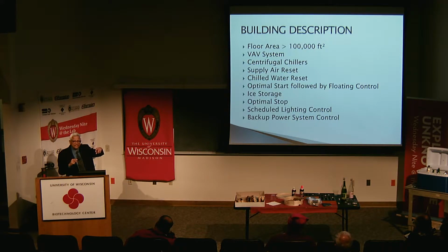Of course, it results in a little bit of extra chiller load, because now instead of keeping it at 78, you are using the optimal start to keep it at 73. But remember, this energy occurs during the off-peak period. So you are paying a lower cost in terms of the chiller energy cost. Now, ice storage. All this means is that during the off-peak time, when the rates are low, you make ice. And you melt the ice during the on-peak period, when the rates are high. There could be a partial ice storage system or a full ice storage system. That really depends on the designer's viewpoint. And of course, full storage is normally not used, it's expensive.